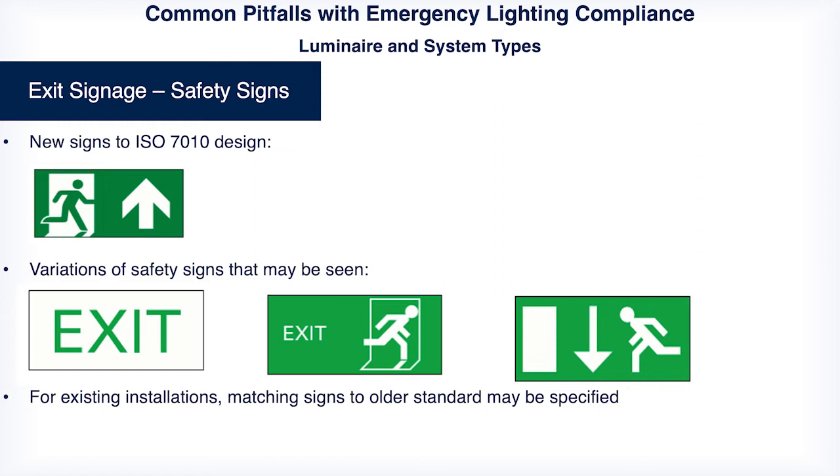The most common use, of course, these days is the down arrow above a final or transient doorway, and the down arrow is now only to be used at the top of a downward staircase. So at all door exit points where there is no change of direction downwards, the upward signage is the one that should be used to indicate that you're going forwards or ahead. This downward signage was deemed too clear an indication that you were going downwards.